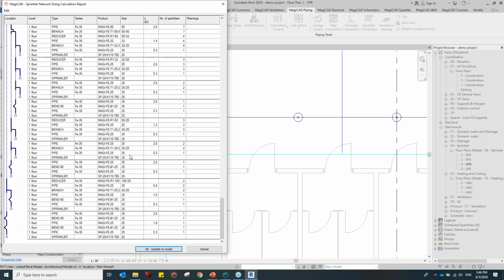Based on my table, every 3 sprinklers - 1, 2, 3 - after 3 sprinklers there must be a different size, 25 or 32 for example. If you look at these 3, and this is the 4th sprinkler, 25 here for 3 sprinklers, and more than 3 will automatically jump to the given table size.